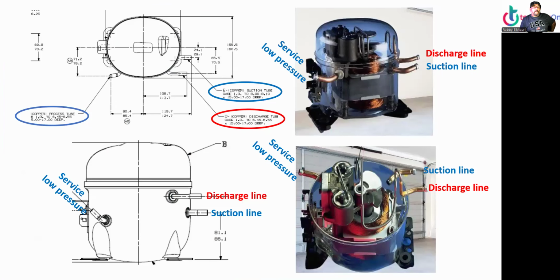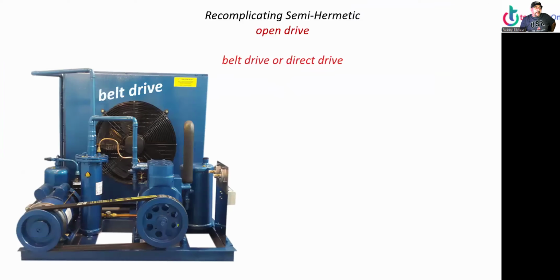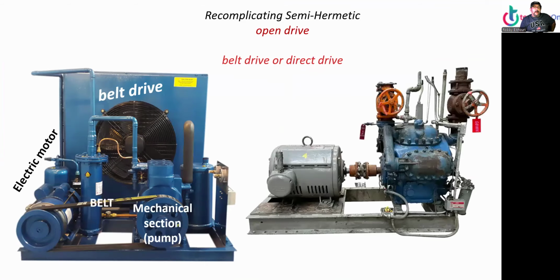Now, this one, it's good to look at the diagram and figure out which one it is. But you can see the suction, the blue, is at the bottom, and discharge on top. With pictures, it's best to look at the diagram. When you replace a compressor, you replace it with the right one, but it doesn't hurt to look at the diagram. Sometimes they change on you. Every compressor comes with paperwork. All right, now we have belt drive, an electric motor, mechanical from the outside, the pump, and the belt. Or we have direct drive, connected by a direct drive connection. Alrighty.